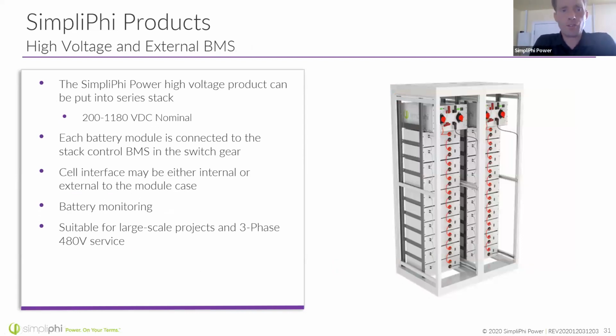Here's what it looks like for one of the high voltage stacks. Again, these stacks can go all the way up to 1200 volts nominal DC. The 48 volt stack is what I'm showing here. You can tell because it has a stack controller on both of the stacks. With 24 volt modules you only need a single controller for 2 stacks. But these can go all the way up to 1180. Almost everything that requires 3-phase 480 service is a good fit for these high voltage stacks. And again, they can come in very large systems, in a 24-foot shipping container or even a 48-foot shipping container. And we have solutions if you have very big projects like that. The cell interfaces allow communication between the individual modules. You can see those communicating cables running up here. And then the stack controller is controlling the overall charging of this system and monitoring.